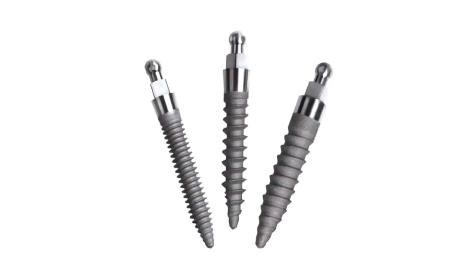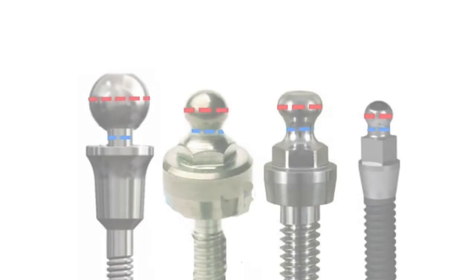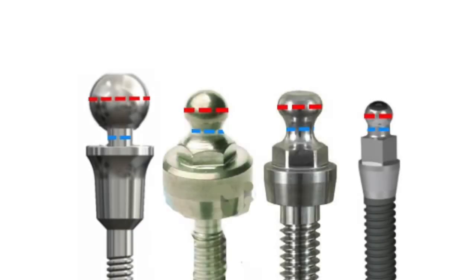When you're working with mini implants that have flats cut into the side of the ball — it's not a full 360-degree sphere — you need to stick with the o-rings. Keep in mind the key factors: measure the diameter of the ball or measure the neck. Once you have that information, we have everything you need to help you service that patient. Thanks for being here today, we'll see you next time on Tech Talks.